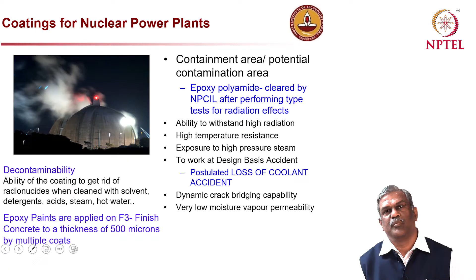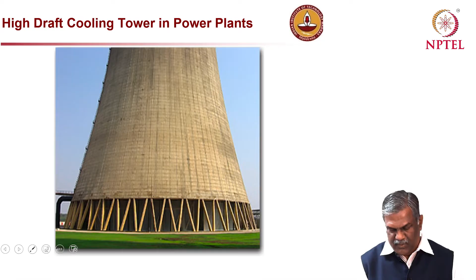The second important area is in thermal power plants where you have a high draft cooling tower. Water continuously keeps falling inside at a high temperature of 35 or 40 degrees, and it has to be cooled down before consumption. This water is in continuous contact with the concrete structure, so water and temperature are not going to go well with concrete, and you might have a lot of issues with respect to the penetration of water, neutralization of the concrete, and the corrosion happening there. So we require a coating applied when the concrete is dry. That's fine, many coatings are there, but epoxies are not to be applied on a wet substrate, or on a substrate contaminated with oil or grease. So when you look into these conditions, no coatings are workable in this type of structure during maintenance painting.